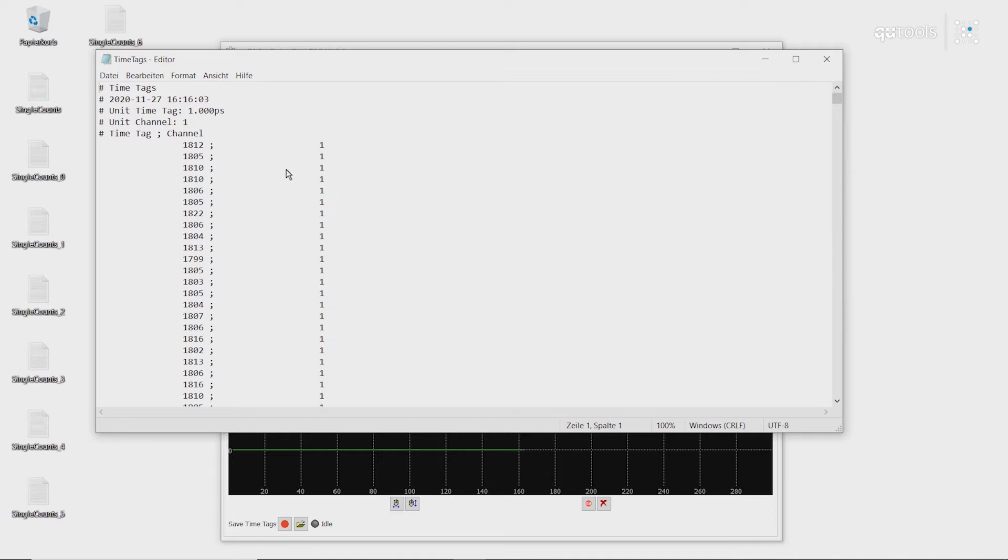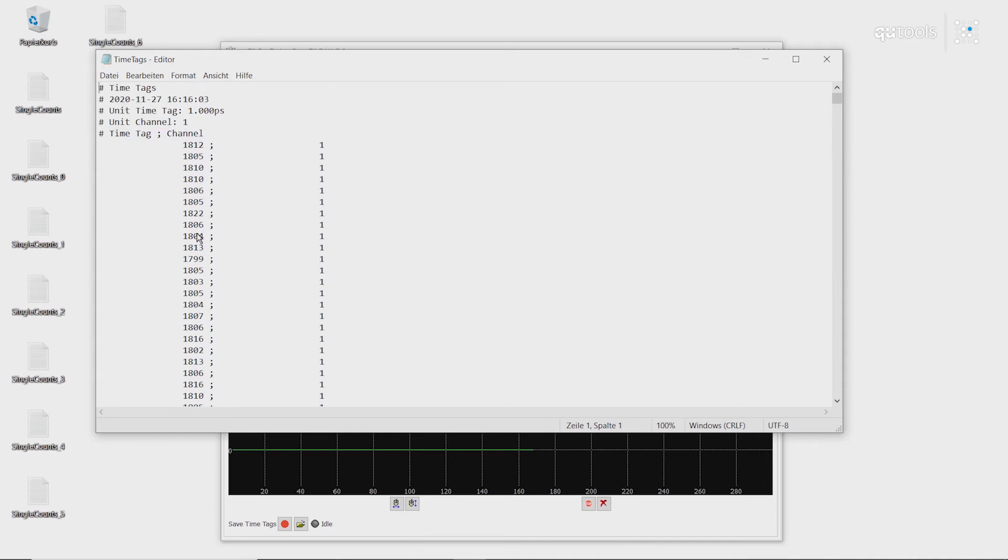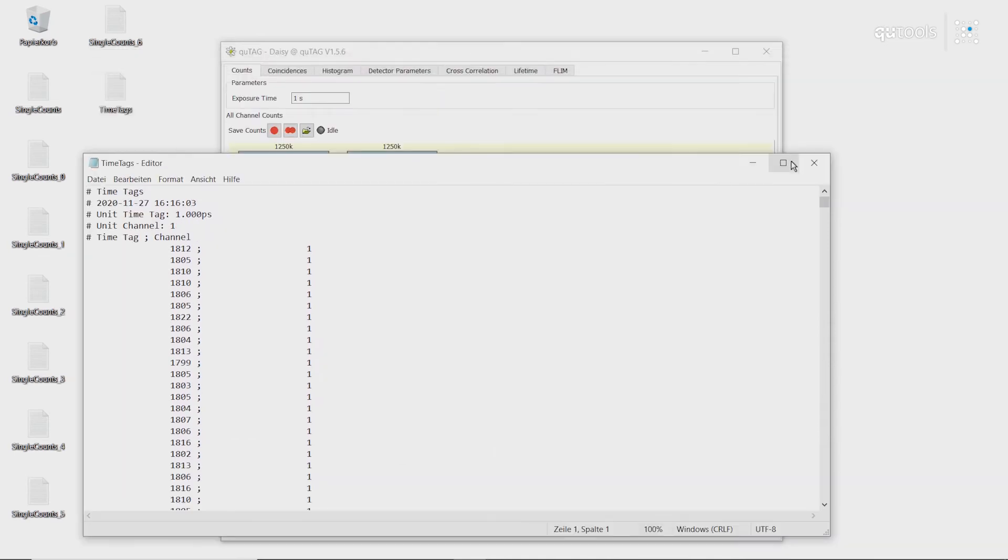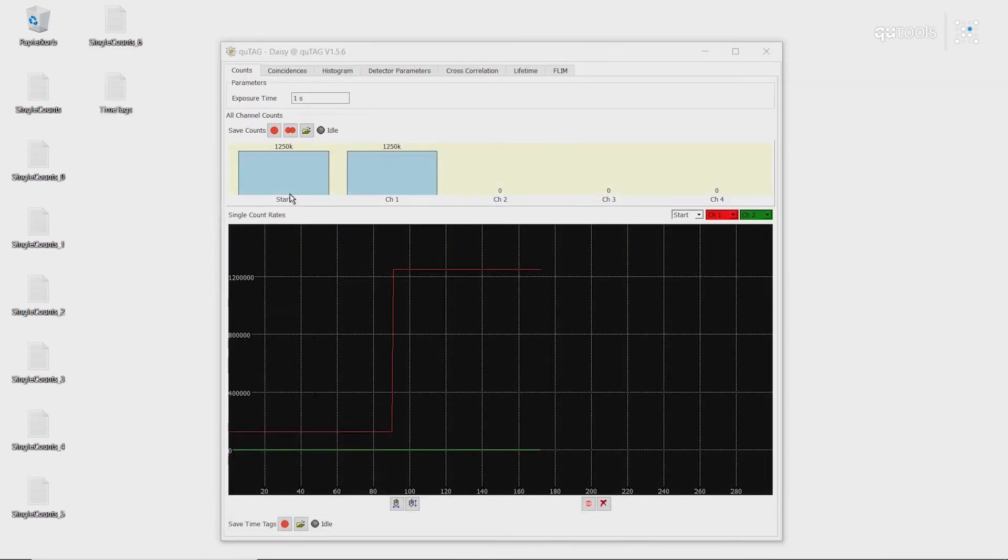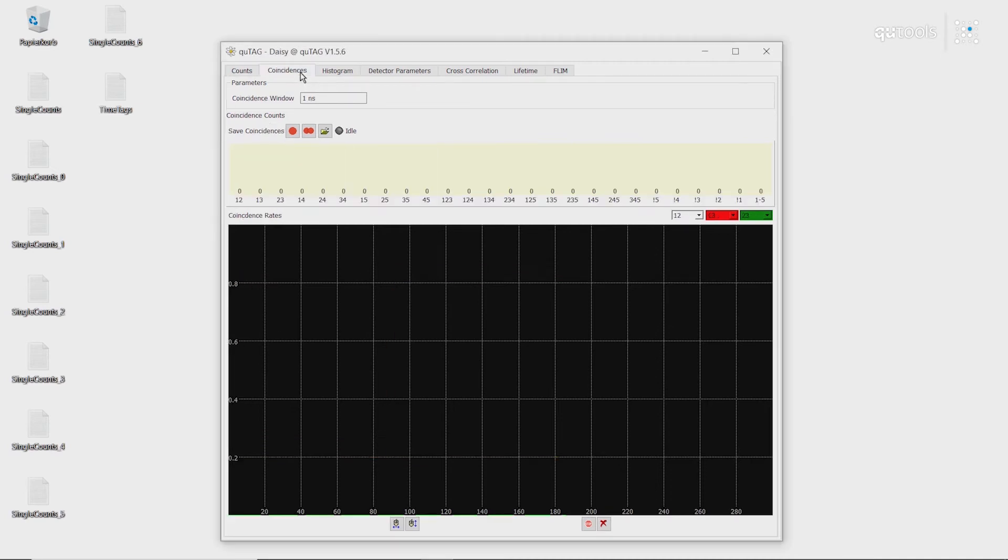As you can see, we have many events on channel 1, all around 1800 picoseconds. This is because the start channel is set with a cable that has a slightly shorter length than cable 1. So we have a slight time delay between the two channels. We can see this in our coincidences.